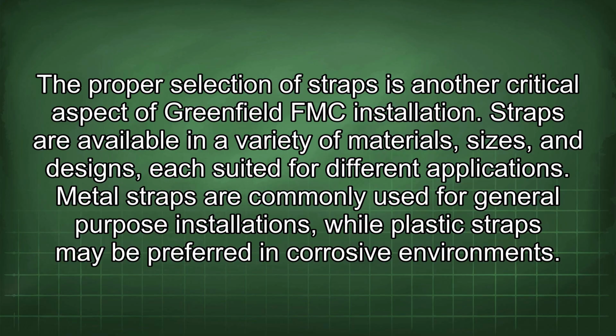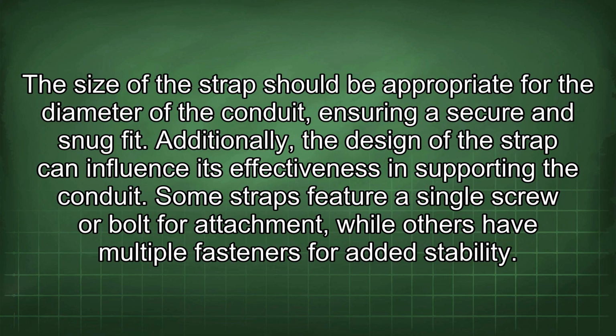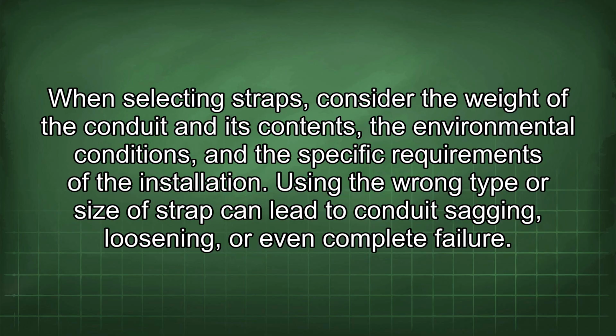Straps are available in a variety of materials, sizes, and designs, each suited for different applications. Metal straps are commonly used for general-purpose installations, while plastic straps may be preferred in corrosive environments. The size of the strap should be appropriate for the diameter of the conduit, ensuring a secure and snug fit. Additionally, the design of the strap can influence its effectiveness in supporting the conduit. Some straps feature a single screw or bolt for attachment, while others have multiple fasteners for added stability. When selecting straps, consider the weight of the conduit and its contents, the environmental conditions, and the specific requirements of the installation. Using the wrong type or size of strap can lead to conduit sagging, loosening, or even complete failure.